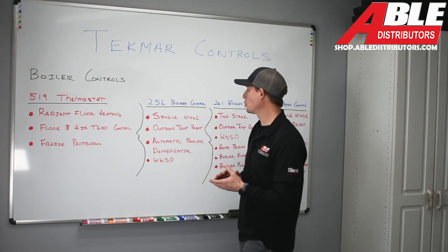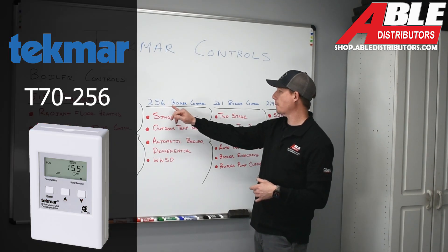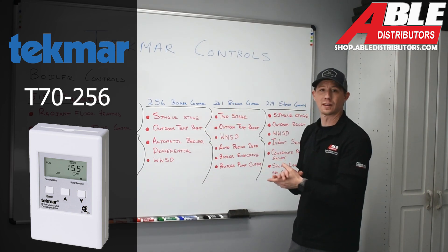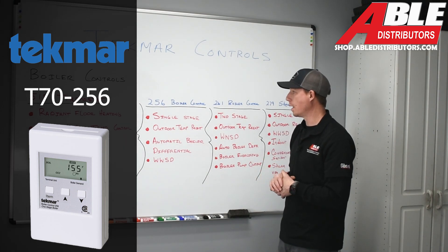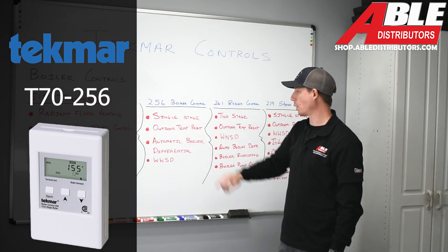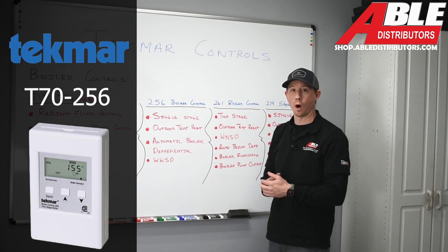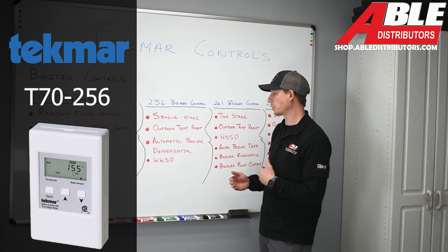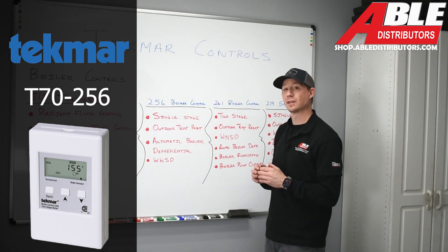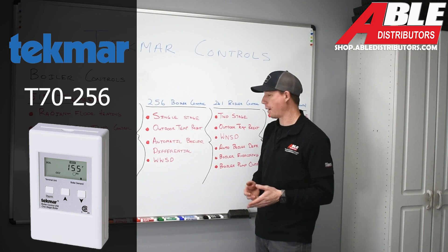Now we're going to dive into three different types of boiler controls sold at Able Distributors. We're going to start with the 256 Tekmar boiler control. This is not a thermostat — this is a control that talks to the boiler and tells it what to do based on the data you provide. The 256 is a single stage boiler control. It accommodates an outdoor temperature reset, meaning it adjusts water temperature based on outdoor temperature, and it provides an automatic boiler differential — telling the boiler when to turn on and off on its own.